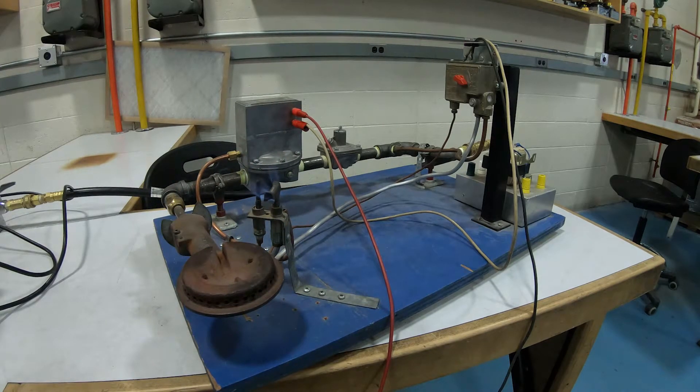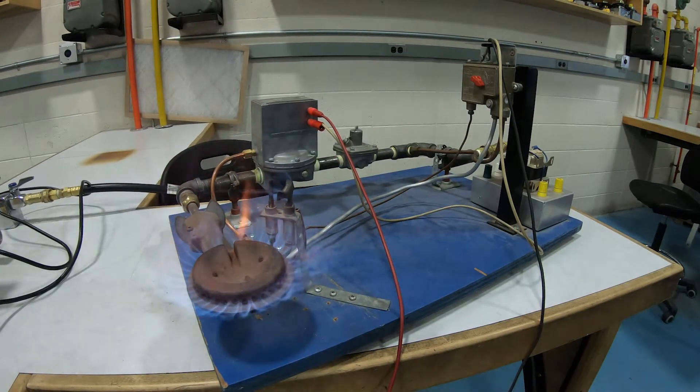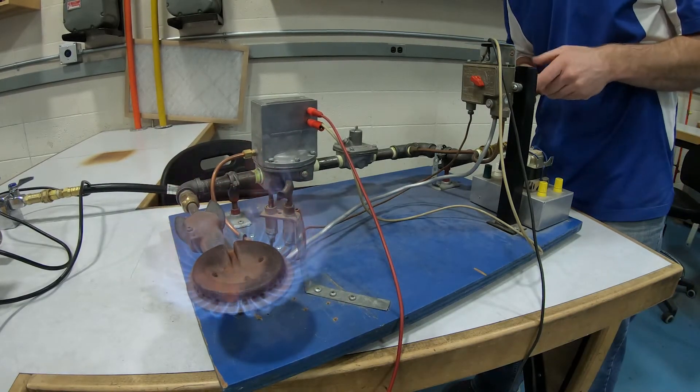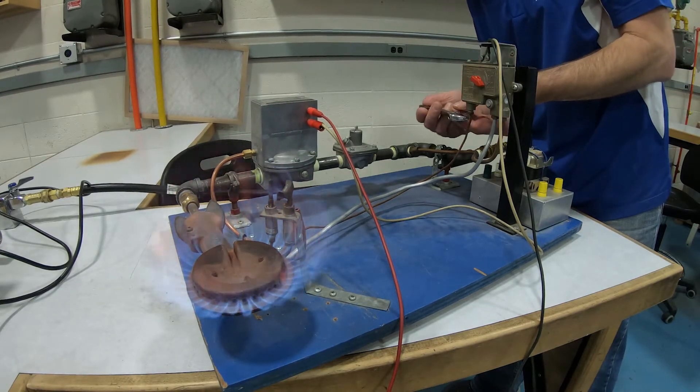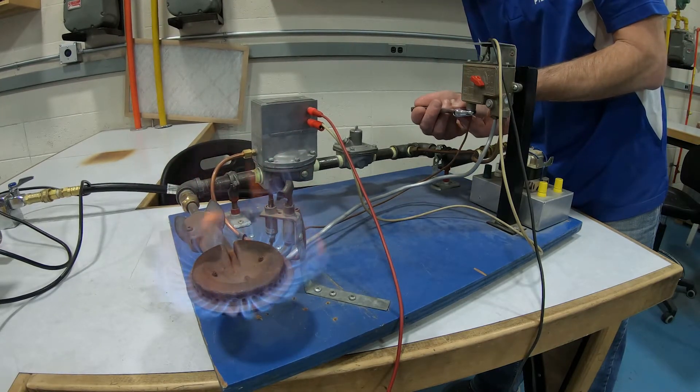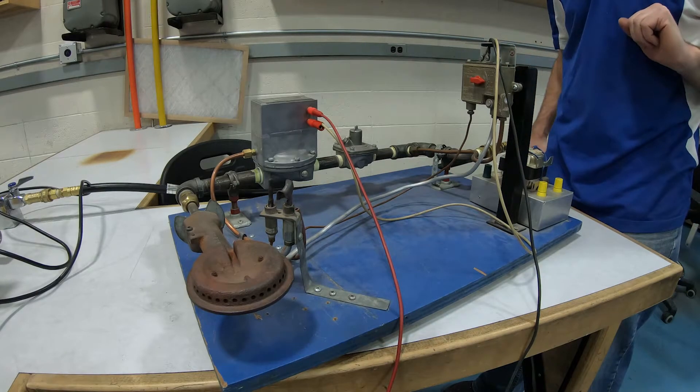Now let's try to simulate a fault with this one. So there we go. We're burning. And I'm going to simulate the thermocouple or the pilot assembly blowing out by just loosening the thermocouple. Let's see what happens to everything. Everything shuts off. Gas to the pilot, gas to the main burner, off. 100% safe, shut off.